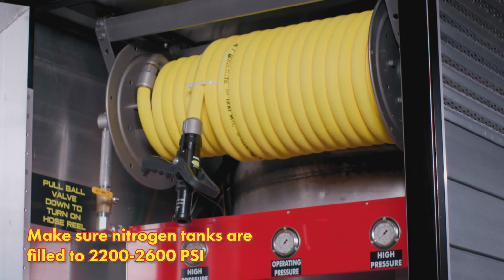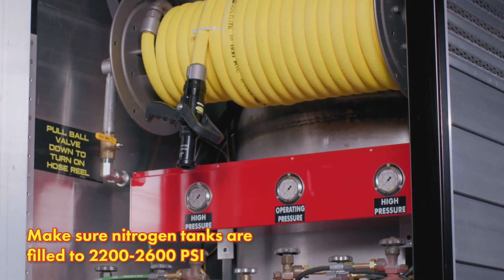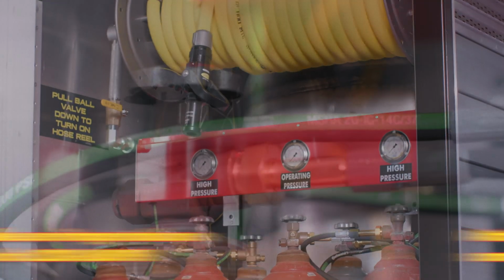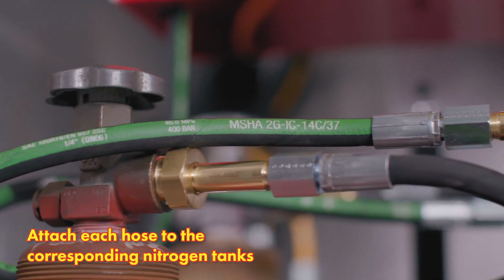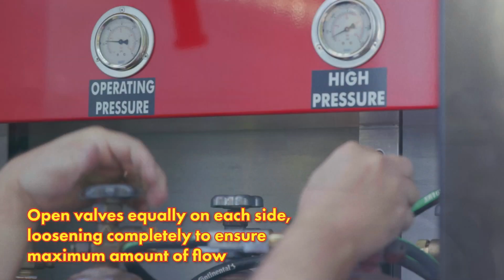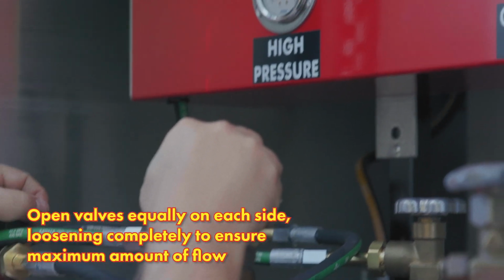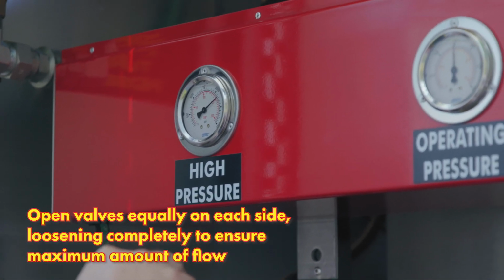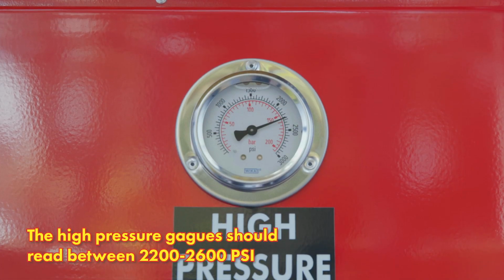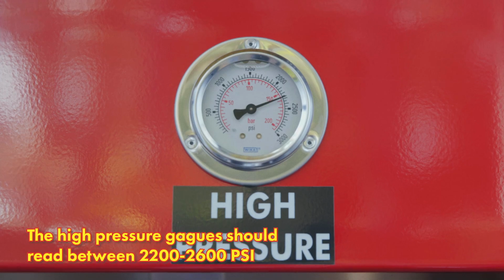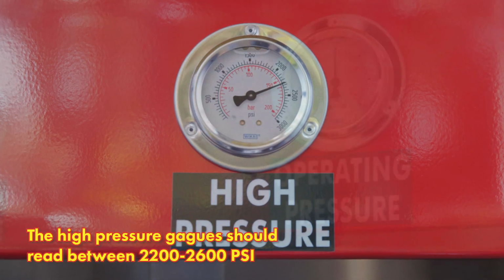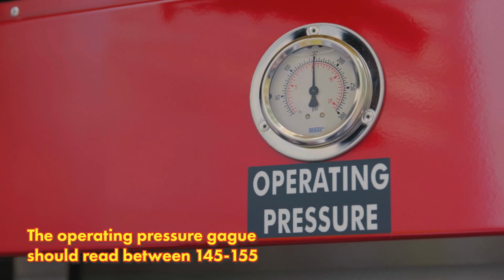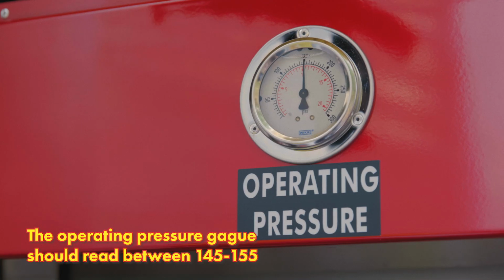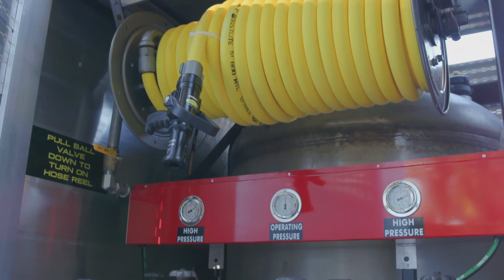To charge the unit, make sure your nitrogen tanks are filled between 2200 and 2600 psi. Attach each hose to the corresponding nitrogen tank. Open each bottle equally on both sides, loosening the valves completely to ensure the maximum amount of flow. When the unit is charged, the high pressure gauges should read between 2200 and 2600 psi, and the operating pressure gauge should read between 145 and 155. Your unit is now fully installed and armed.